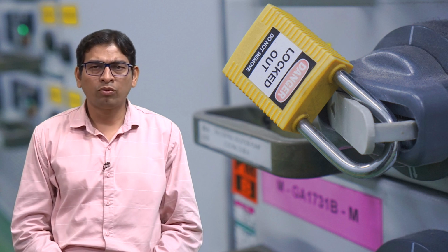Once the temporary restart has been accomplished, normal procedures must again be followed to reinstall the lockout tagout devices and isolate the machine's energy sources. At the completion of any type of lockout tagout procedure, the locks and tags that have been used must be returned to their homes. They should also be signed in on the lockout tagout log, if one is being used.